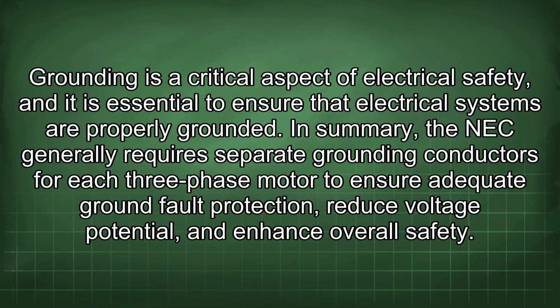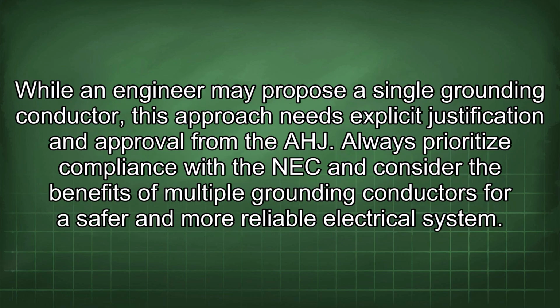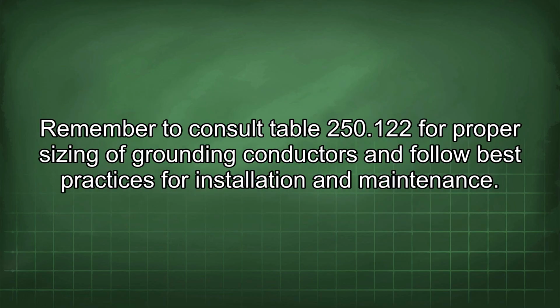In summary, the NEC generally requires separate grounding conductors for each three-phase motor to ensure adequate ground fault protection, reduce voltage potential, and enhance overall safety. While an engineer may propose a single grounding conductor, this approach needs explicit justification and approval from the AHJ. Always prioritize compliance with the NEC and consider the benefits of multiple grounding conductors for a safer and more reliable electrical system. Remember to consult Table 250.122 for proper sizing of grounding conductors and follow best practices for installation and maintenance.